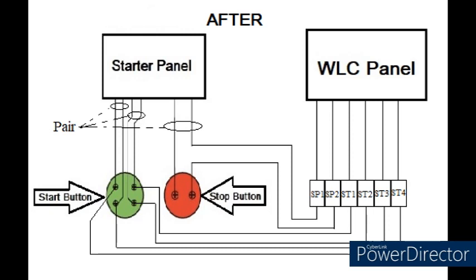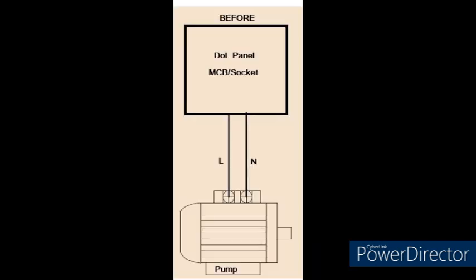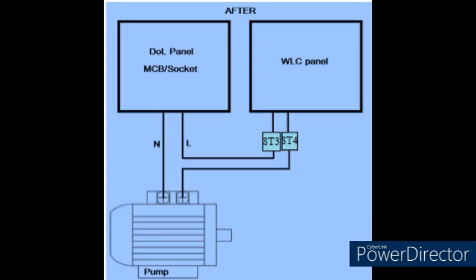Caution. It is mandatory to identify the pairs in the start button of the feeder if it has more than 2 terminals. It can be done with a multimeter and they are separated by the mounting screw of the back element of the push button. In the picture, left side top and bottom terminals are a pair and are separated by the mounting screw. Similarly, right side top and bottom terminals are a pair and are separated by the mounting screw in between. If the feeder is DOL, MCB, socket type, then as shown in the pictures, the phase line is disconnected from the motor and connected to ST3 of WLC, and ST4 of WLC is connected to the motor.